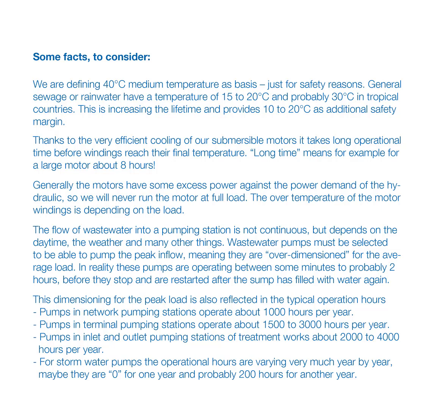This dimensioning for the peak load is also reflected in the typical operation hours. Pumps in network pumping stations operate about 1,000 hours per year. Pumps in terminal pumping stations operate about 1,500 to 3,000 hours per year. Pumps in inlet and outlet pumping stations of treatment works about 2,000 to 4,000 hours per year.